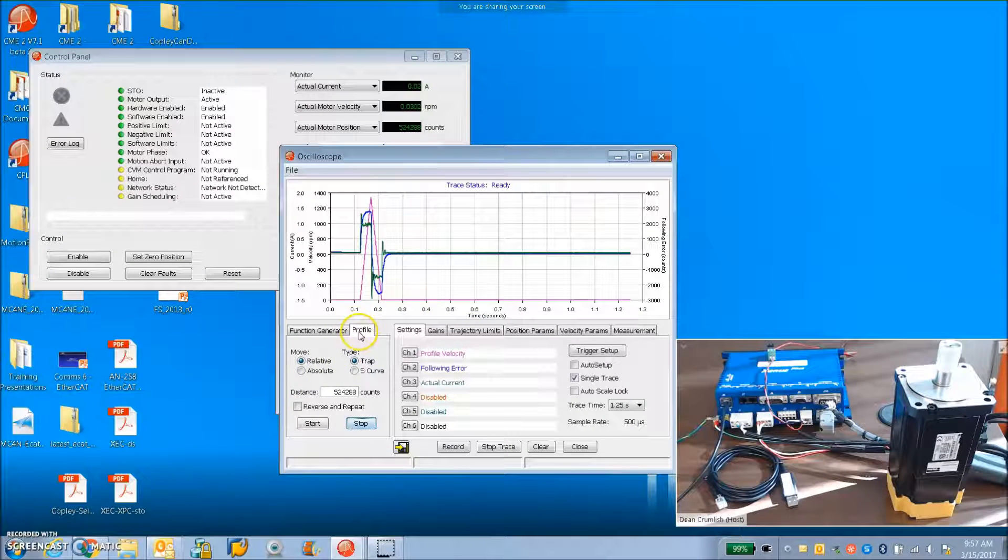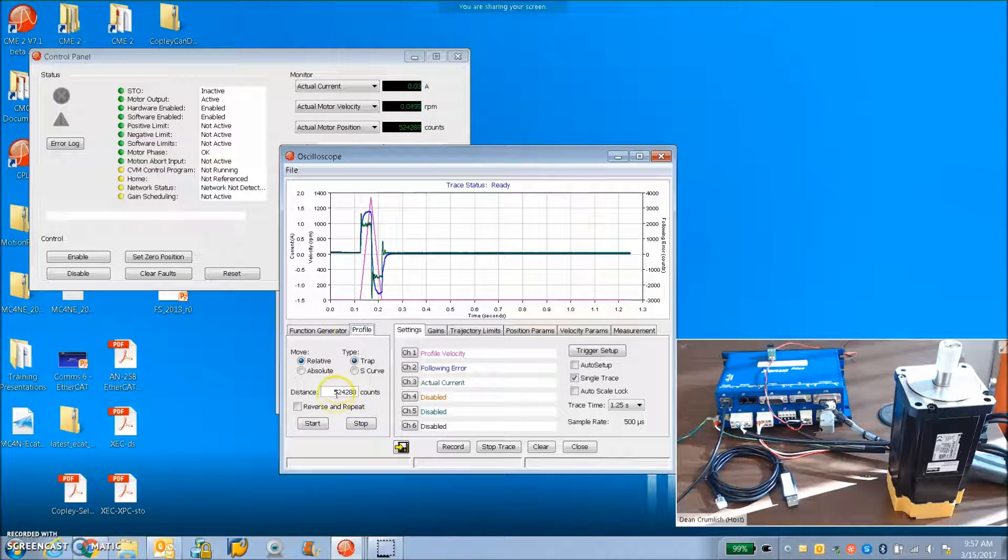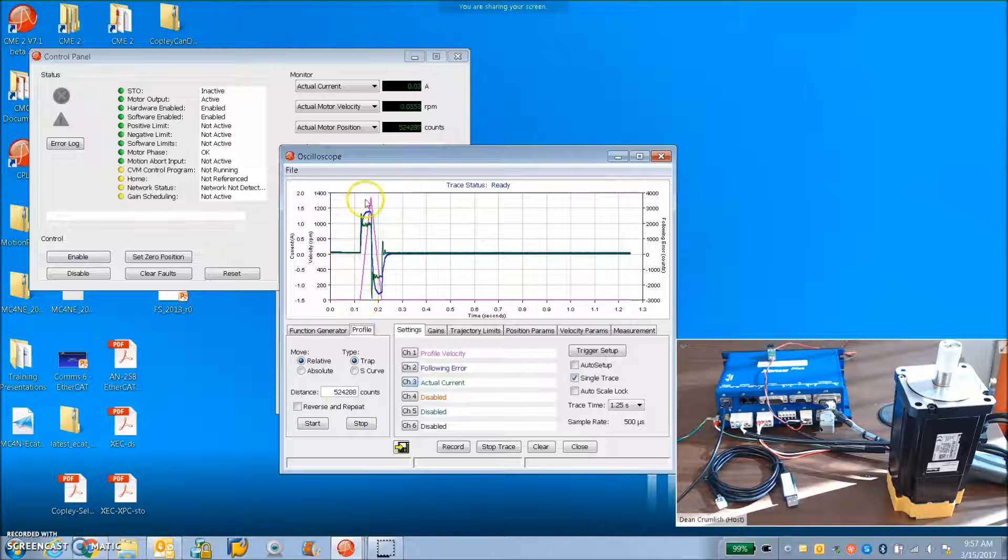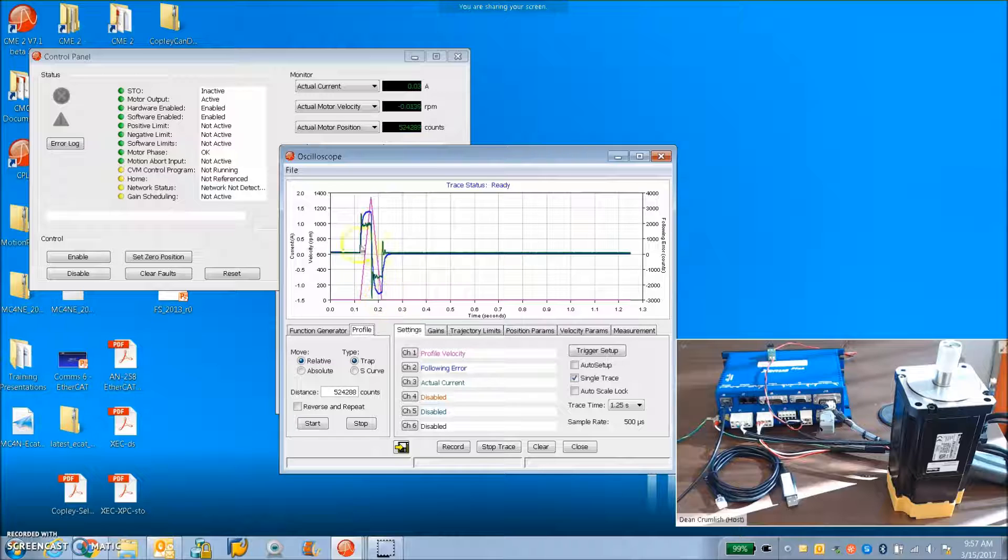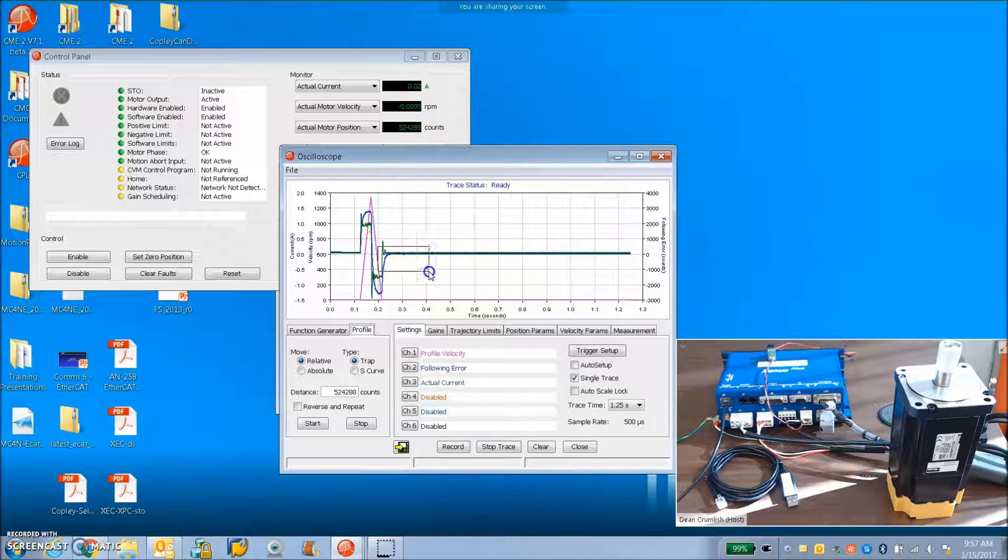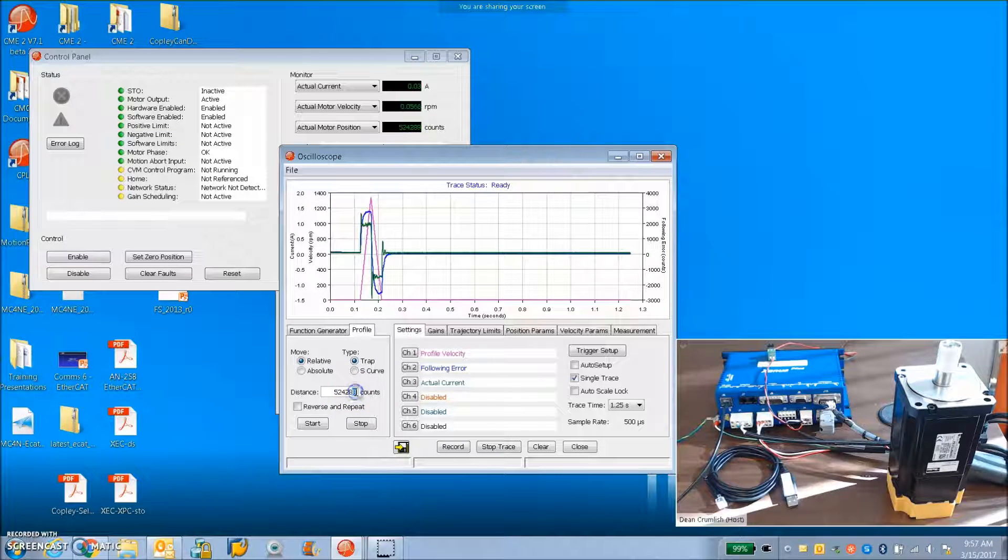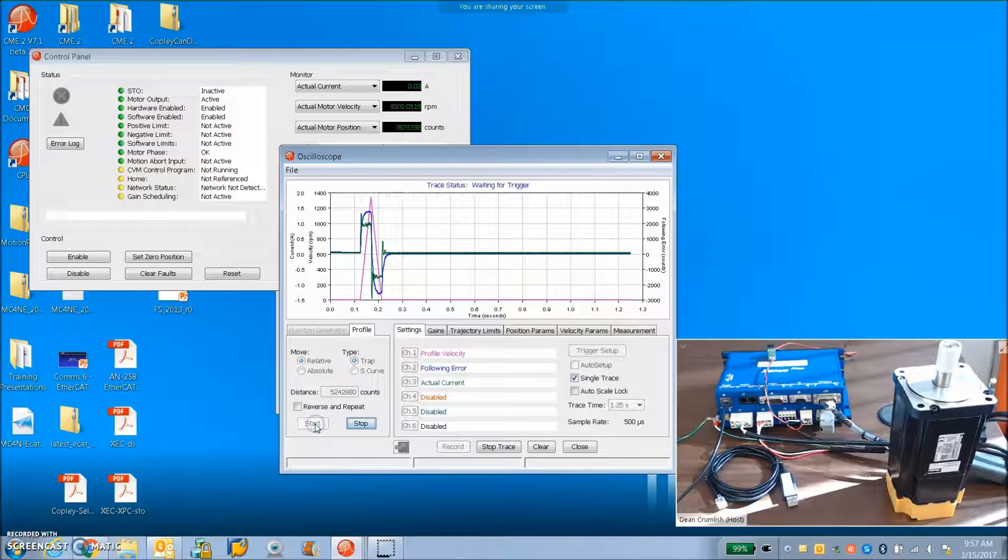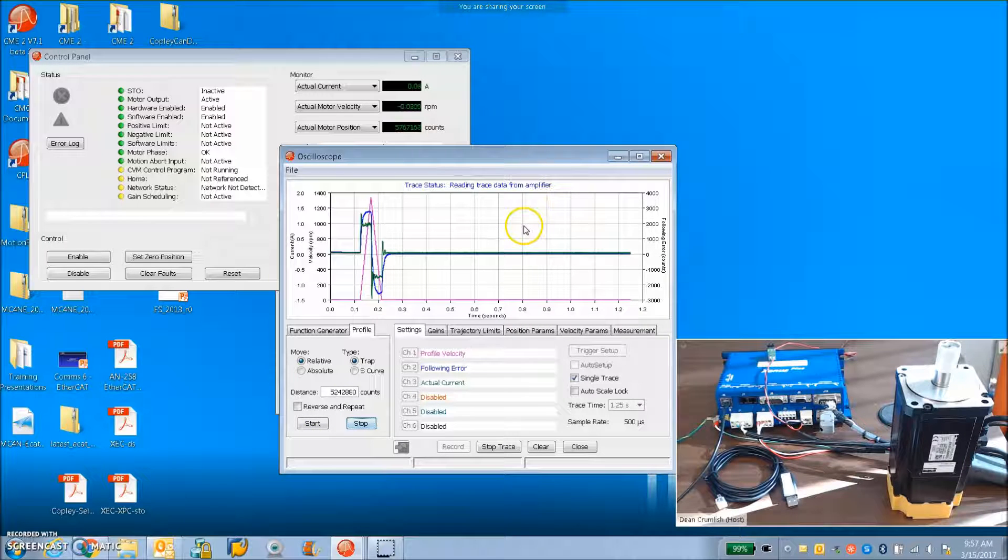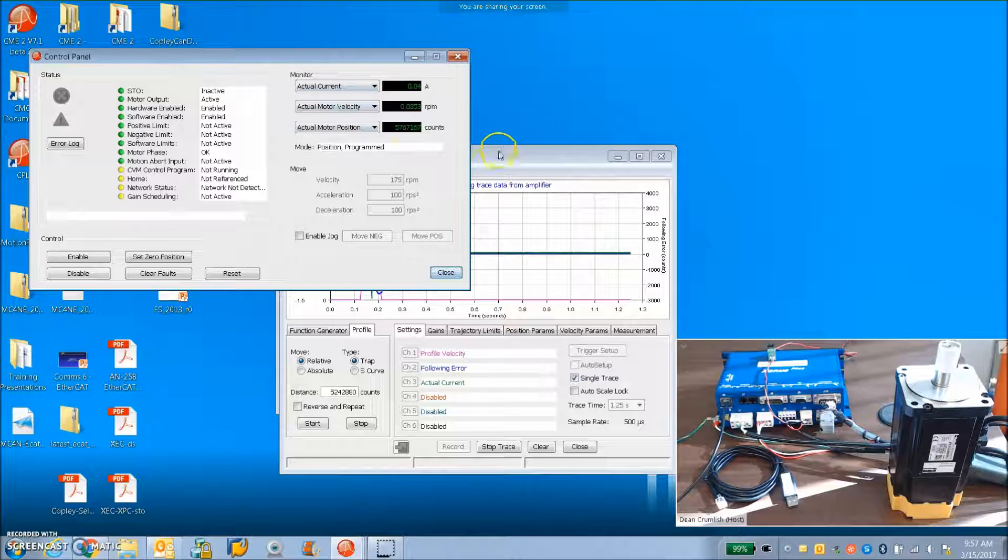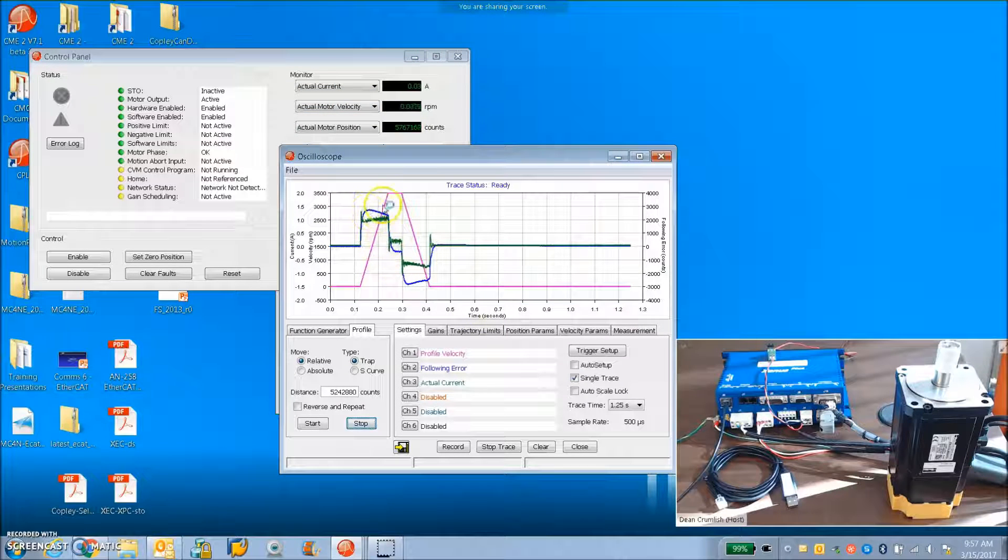Here's the position loop. Profile tab. Auto setup checkbox again. Add the actual current. 524,288 is one rev. You can see the profile velocity, accelerate, run or decelerate. A little peak, plus and minus. A little following error, nice steady state. The integral is not too high. I'm going to add another zero here, we're going to do 10 revs. I got 10 revs of the motor. I can see my actual position there. Run, no problem.